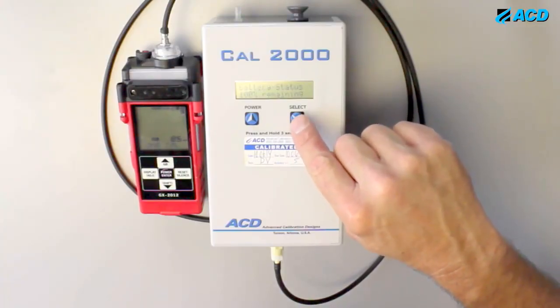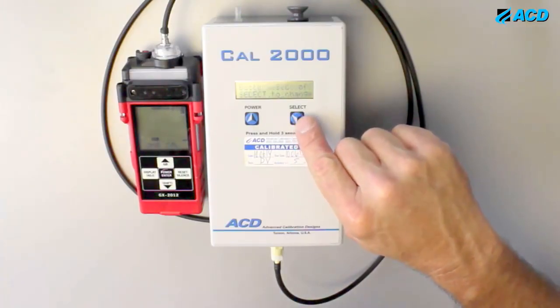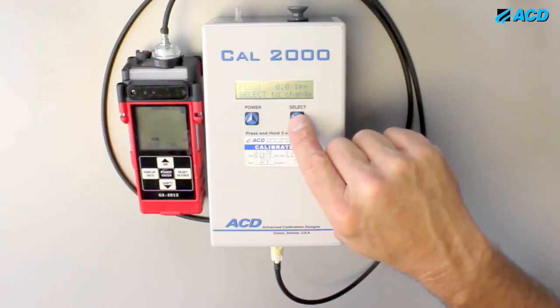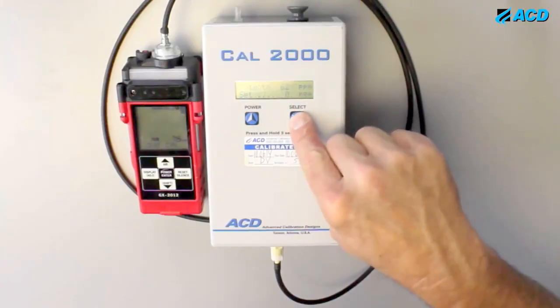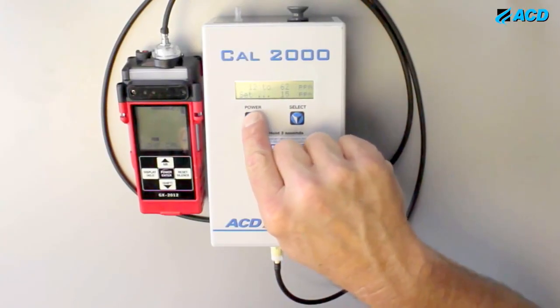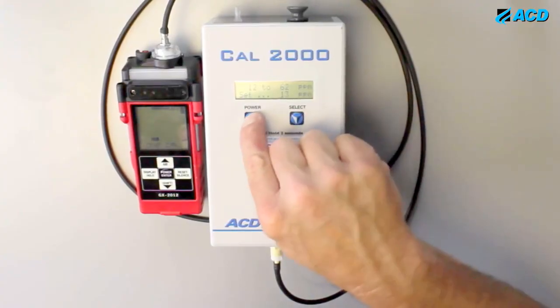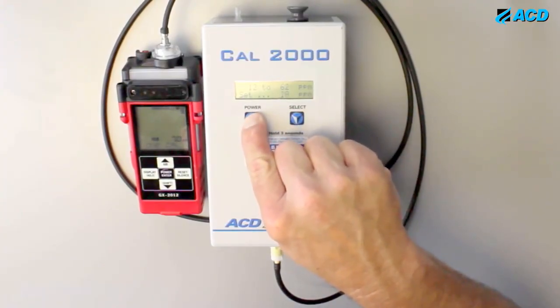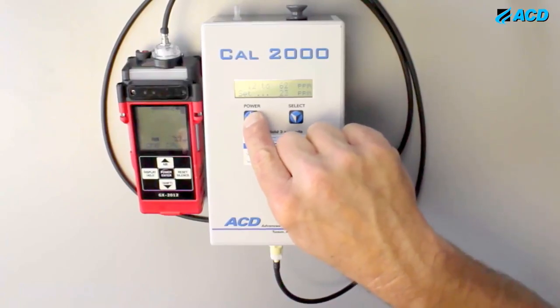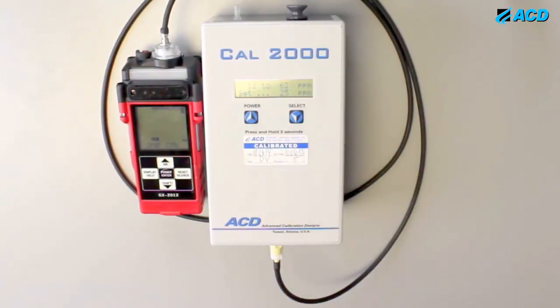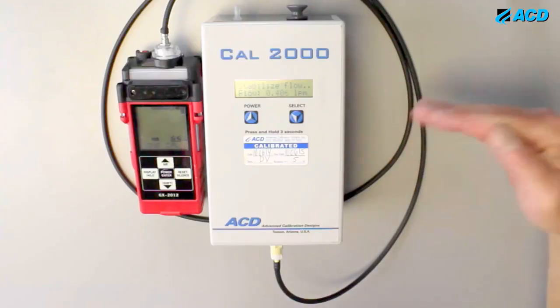Okay. So it's going to go through and show me the flow rate. I've got it set to 0 because I'm in sample draw mode. And I've got 0 parts per million as well. I can select some output. Everybody likes 25. Let's go to 25. So the range on this cell is 0.5 to 50 parts per million. I set it at 25 here. And now it's going to start its stabilization again.